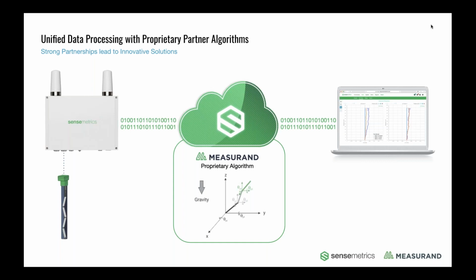The integration consists of two different components. The first component is the retrieval of the calibration file. Once a shape array is plugged into a Sensemetrics thread, the thread will automatically detect the serial number of the instrument and then pull the appropriate calibration file from the Measurand FTP server. This reduces the risk of making an error in transcribing calibration files, for example, and ensures that you always have the right calibration file for the instrument installed.